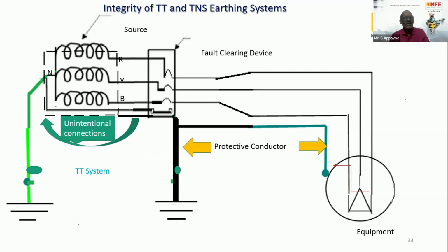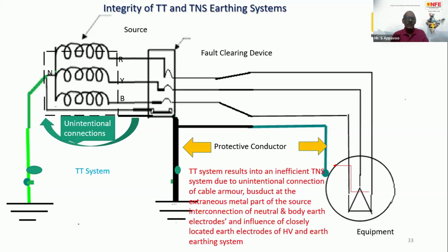What does it mean? Your TT system is becoming weak. Here it is a weak earth fault return current. It's neither a TN-S system nor a TT system. It becomes a weak TN-S system. You have to insulate. Is it happening? So these are the things that we have to take care of while declaring whether we are having a TT system or a TN-S system.